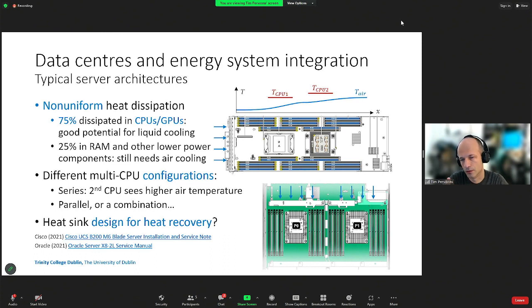So typically, more downstream, you would have higher air temperatures, and therefore the memory modules towards the end of the server, for instance, and the second CPU in the case where you have the series coupling of two CPUs behind each other, the second CPU would see slightly higher temperatures as well. And you can have different configurations. You could have parallel flow or a combination of parallel and series flow.